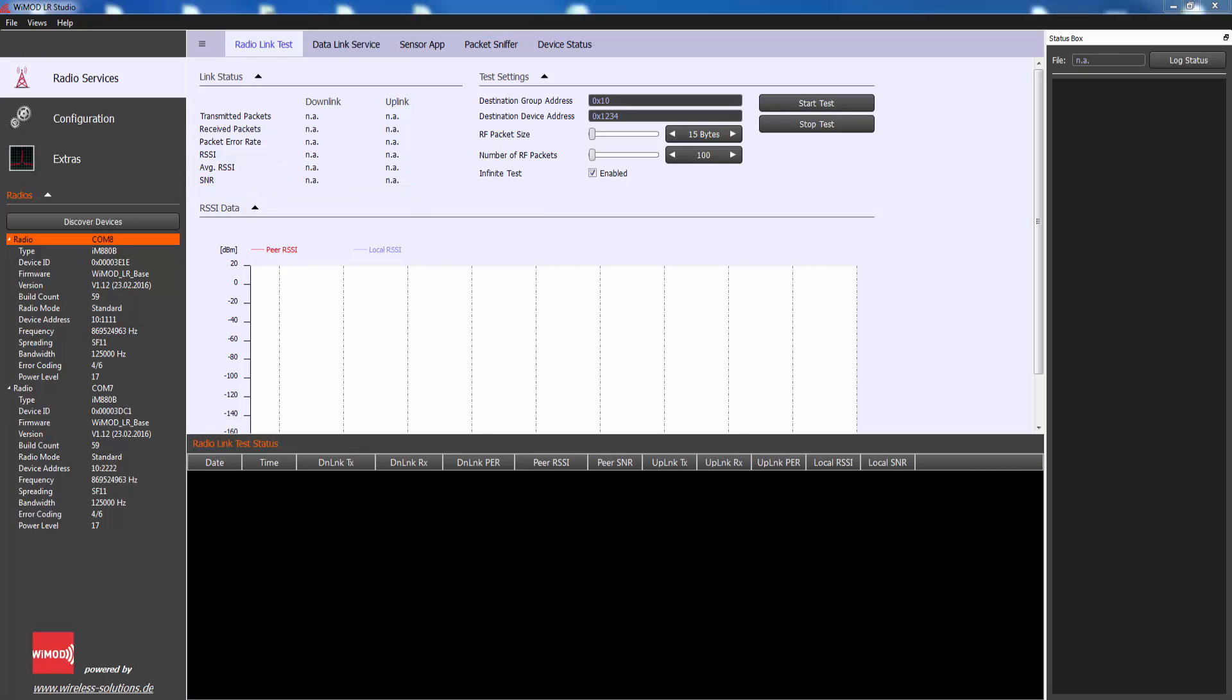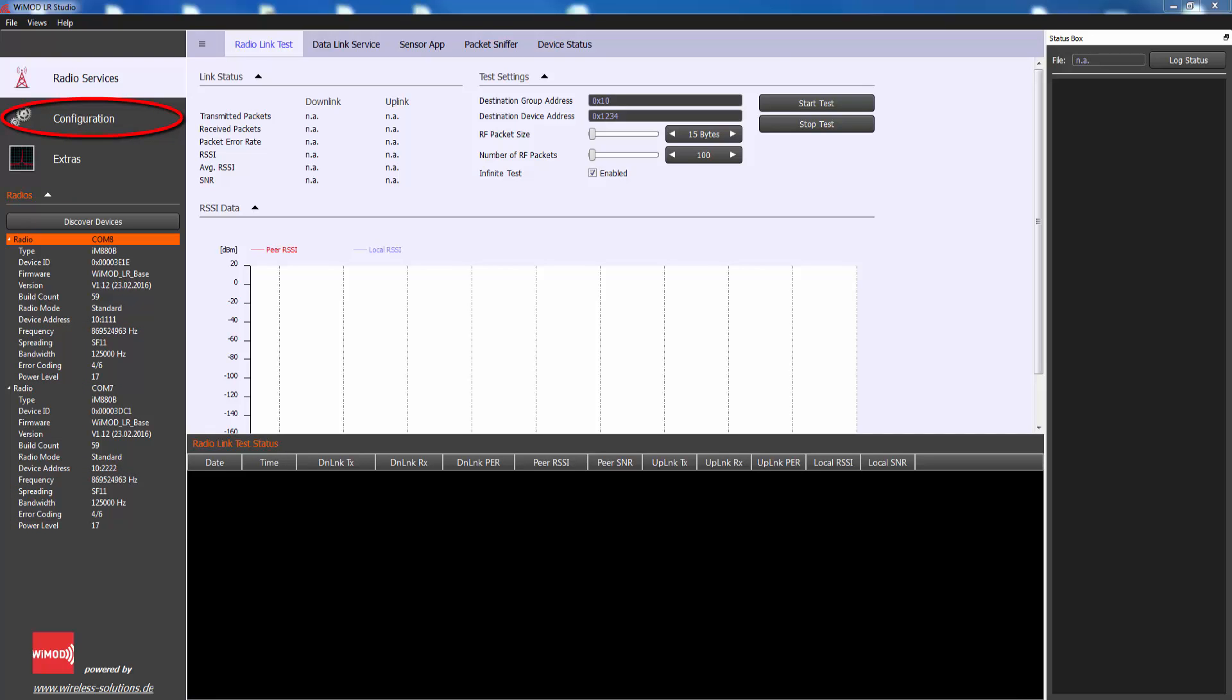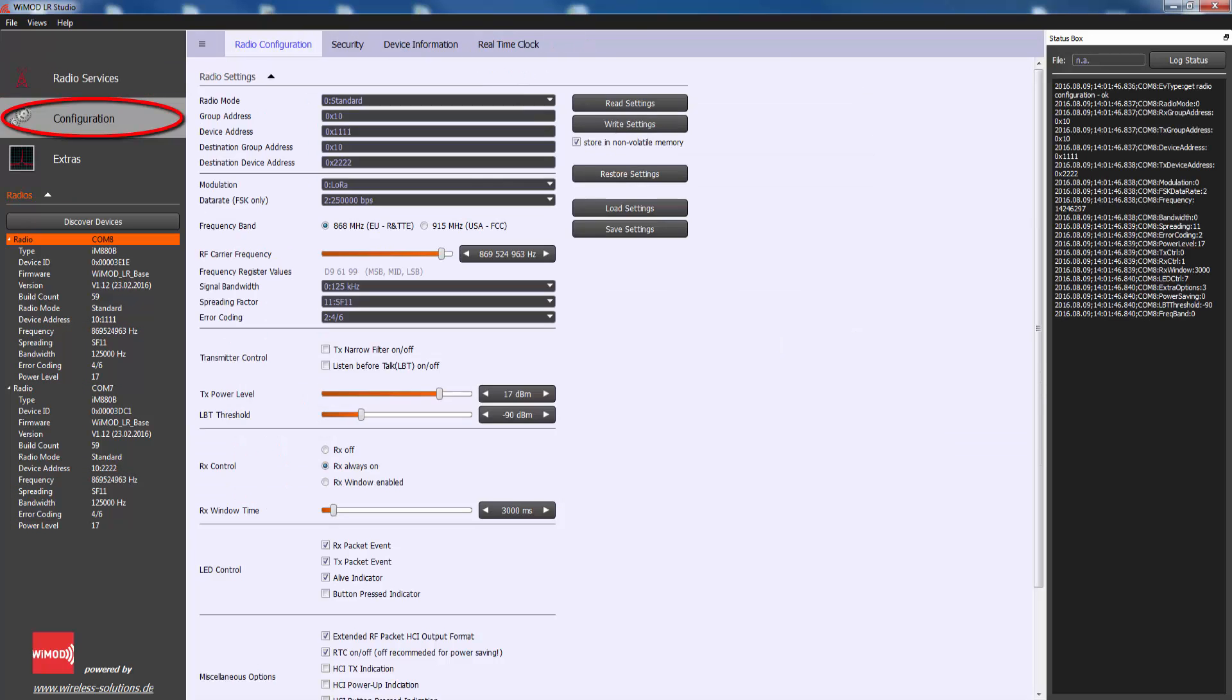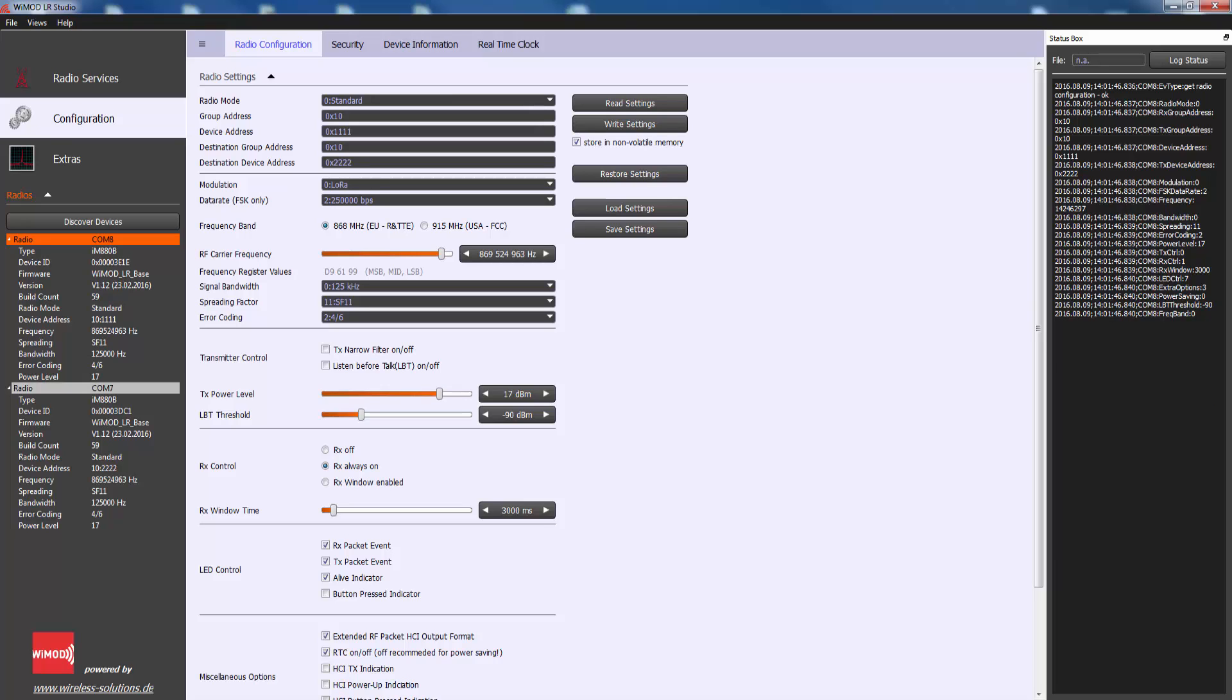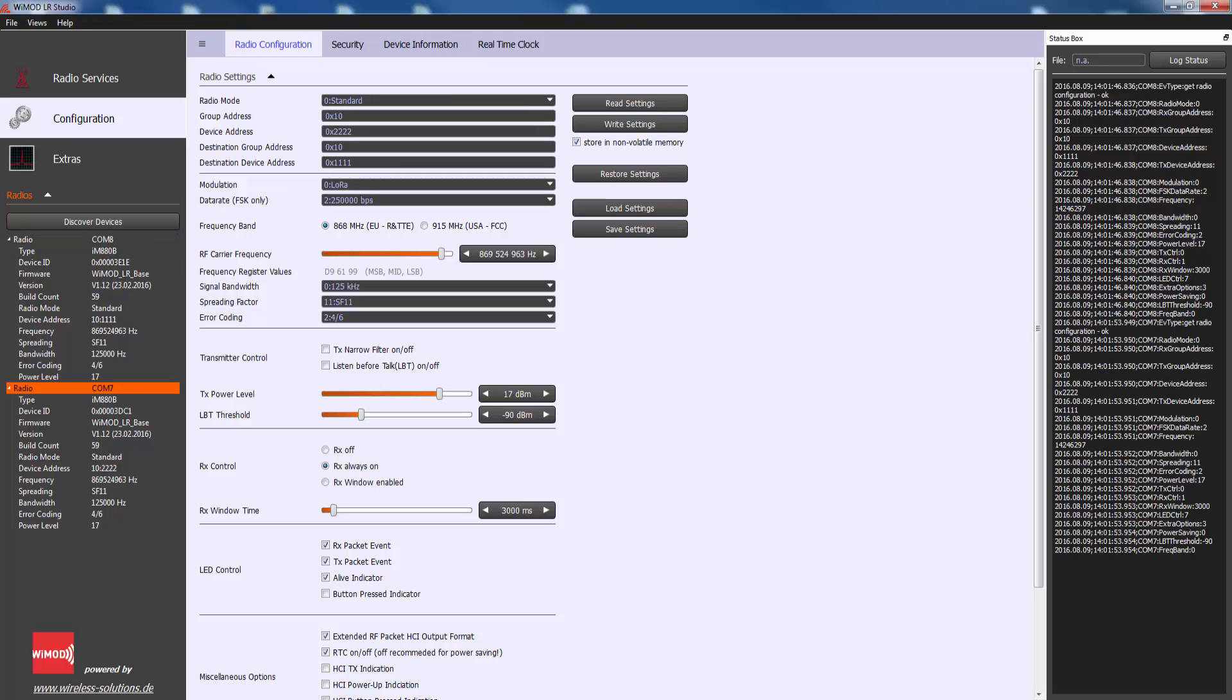To conduct the radio link test, both radio modules must be programmed to the same RF parameters. RF parameters can be set under the configuration menu. If you want to change the RF parameters, you must do this in both radio modules. Therefore, connect both radio modules with the PC and configure the same radio settings.